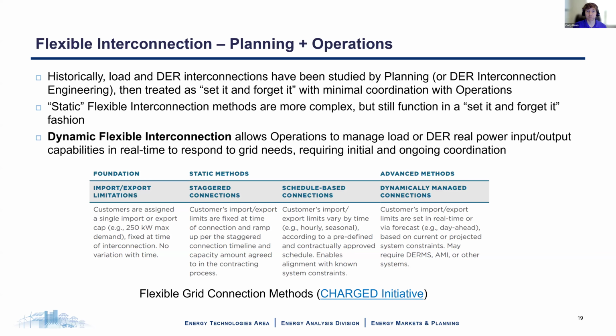Okay. So flexible interconnection is the intersection of planning and operations. Historically, load and DER interconnections are planning's purview. They study it as it is, and it gets connected and it operates, and operations never actually sees or touches it. They just see the little numbers go up when more load or more DER gets added to the system. This is a set it and forget it mentality. You do the study, you fix anything that needs to get fixed so it can connect, and then you plug it in, and operations doesn't have to do anything.